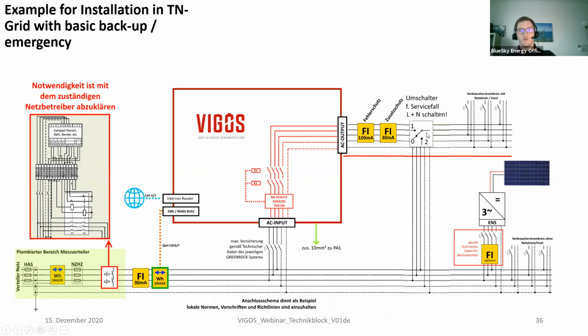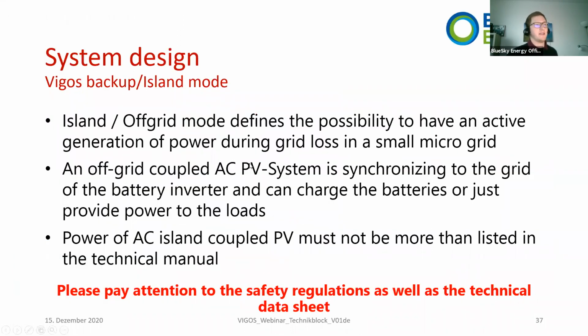And this is just a switch for service. In case of a Vigos failure or if the inverter breaks, you can switch these loads back to the grid if needed. So just in case of a service, we recommend a switch that you can add, so that you can switch these loads, this distribution panel, back to the grid. But if the system is active, you can just keep position 1 so that this is directly connected. In the case of a grid loss or grid failure, these systems stay active. So this is, by our definition, an off-grid system, or let's say an emergency backup system. But it's also possible to do a fully island system with the Vigos, or a backup island system. That means an off-grid coupled AC PV system will also synchronize to the grid of the Vigos, and of the battery inverter, and will charge the batteries or provide power to the loads.